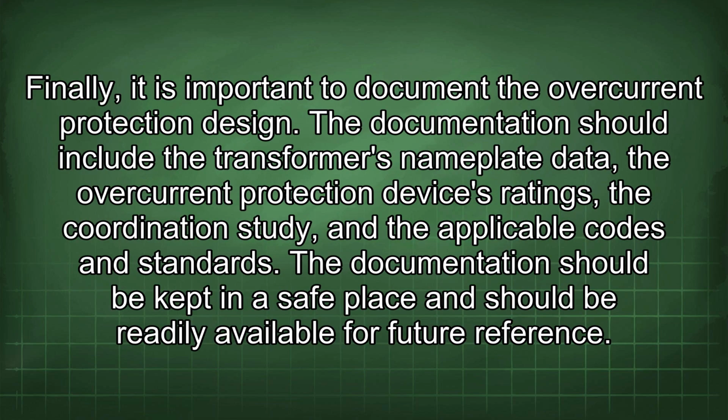Finally, it is important to document the overcurrent protection design. The documentation should include the transformer's nameplate data, the overcurrent protection device's ratings, the coordination study, and the applicable codes and standards. The documentation should be kept in a safe place and should be readily available for future reference.